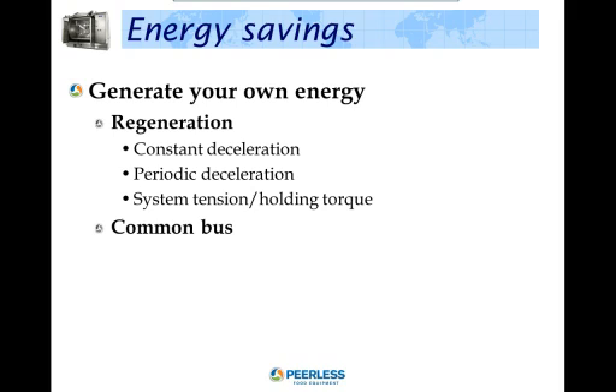Generate your own energy. Some VFD applications enable users not only to save energy, but to regenerate power, which can be routed back to the system or sold to the utility for additional revenue. Regeneration. An AC motor may act either as a motor that turns electrical power into mechanical power or as a generator that converts mechanical power into electricity. It depends on whether the motor is turning a machine that requires power to turn the machine or whether the load of the machine will at times overhaul the motor.